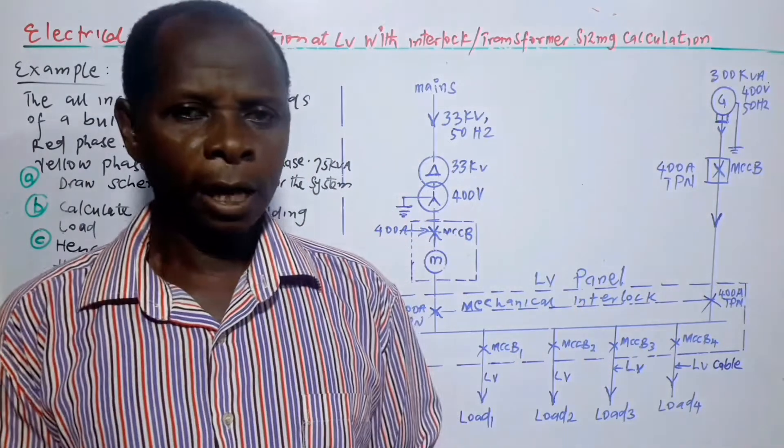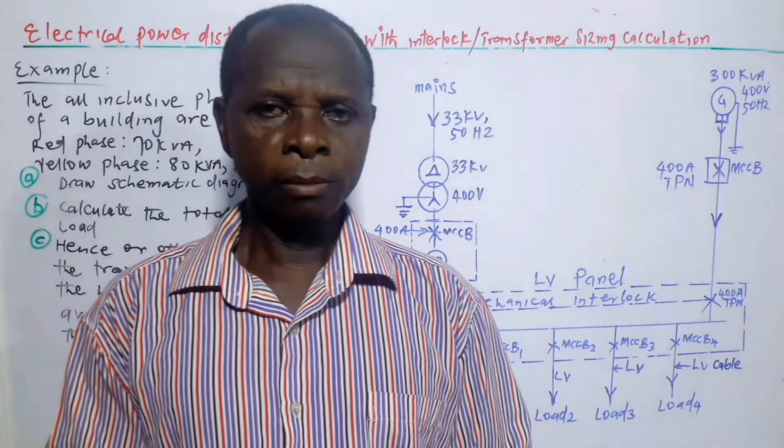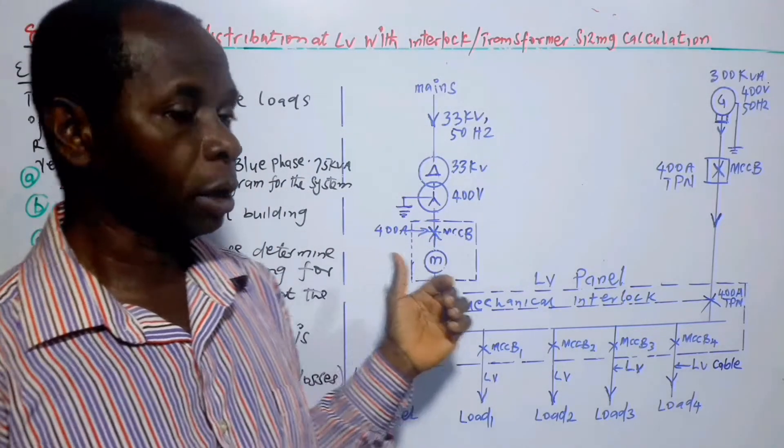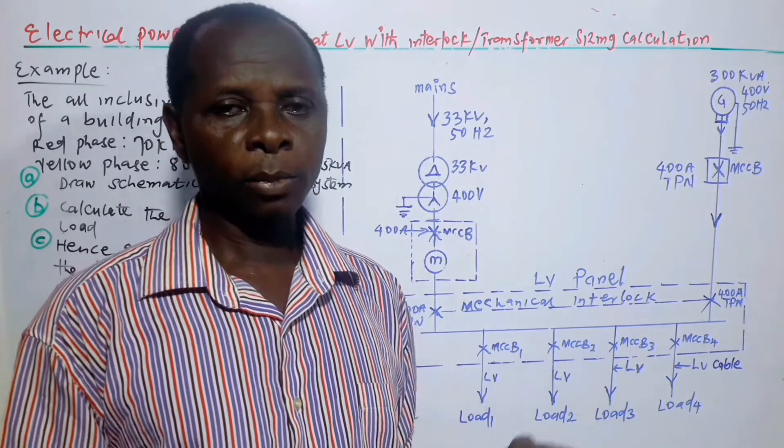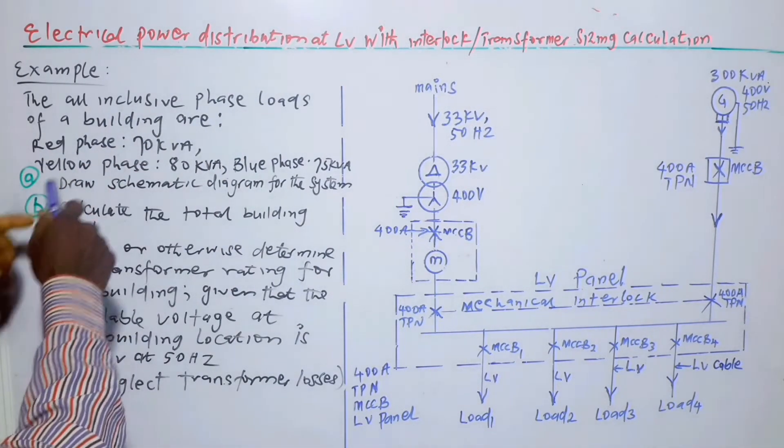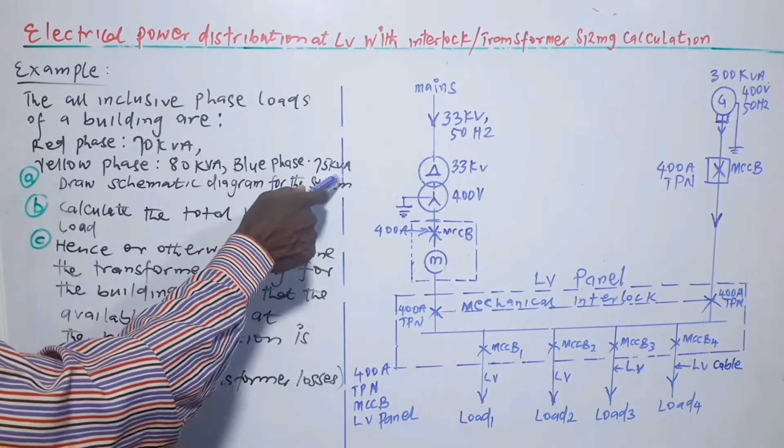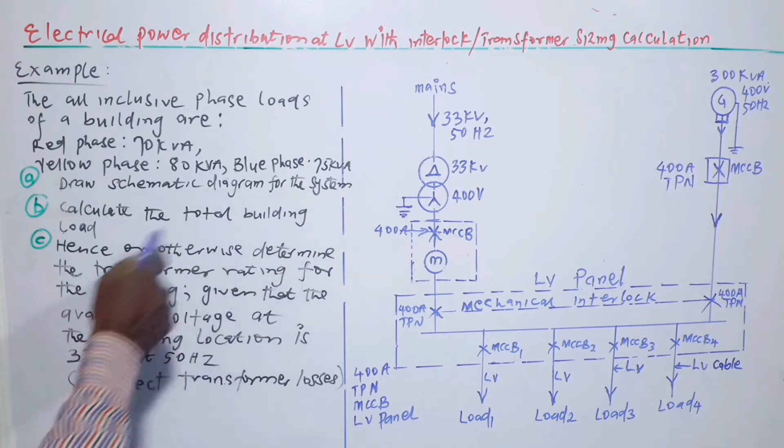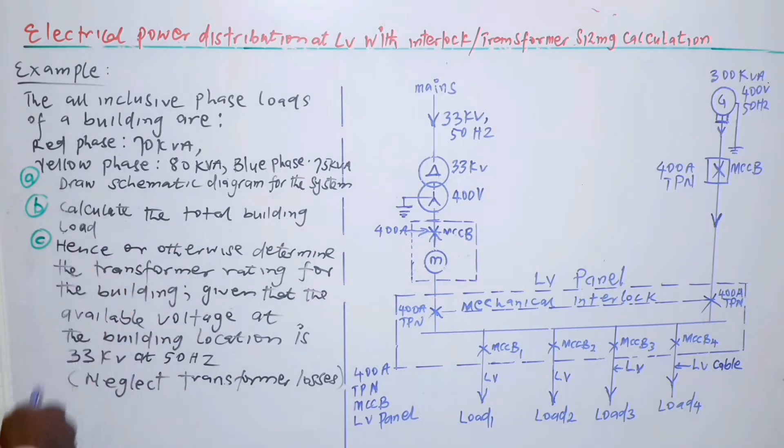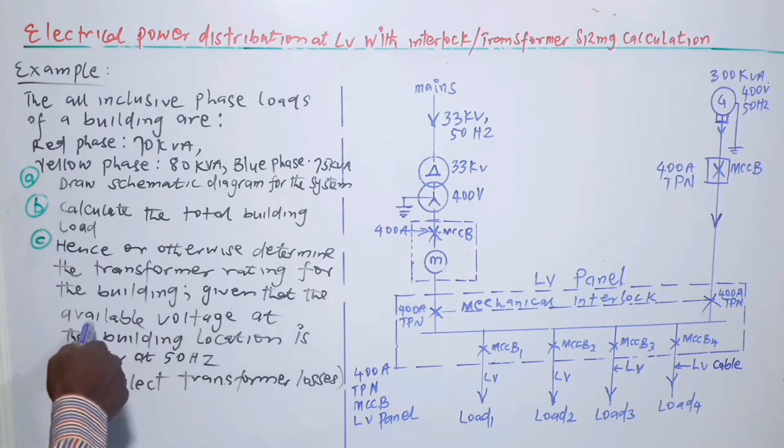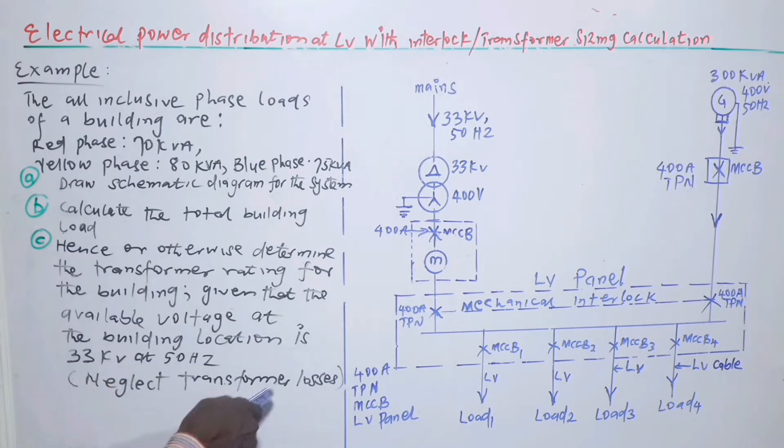For thorough understanding of the concept of power distribution system at low voltage and transformer sizing calculation, the concept is illustrated making use of an example. Example: The all-inclusive phase loads of a building are red phase 70 kVA, yellow phase 80 kVA, blue phase 75 kVA. Part A: Draw schematic diagram for the system. Part B: Calculate the total building load. Part C: Hence or otherwise determine the transformer rating for the building, given that the available voltage at the building location is 33 kV at 50 hertz. Neglect transformer losses.